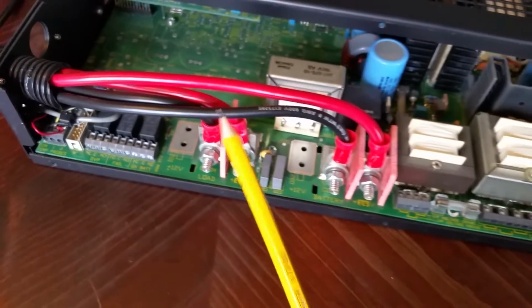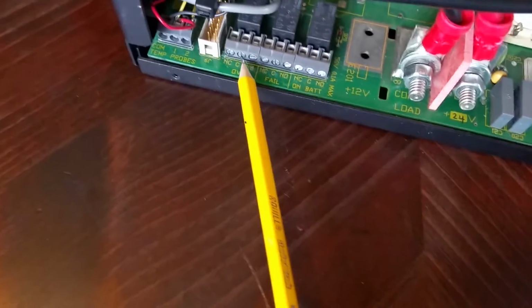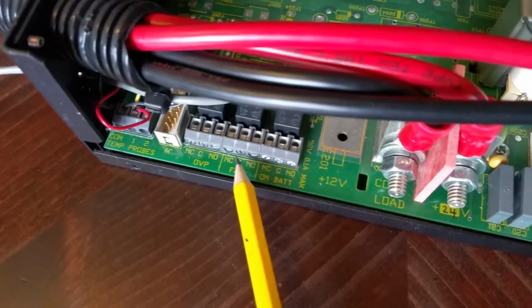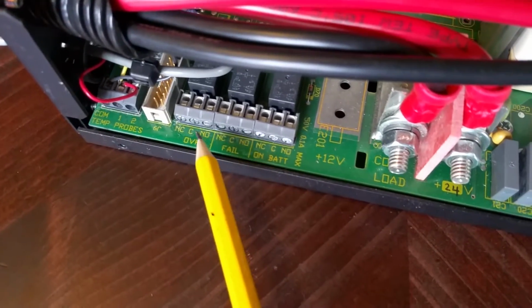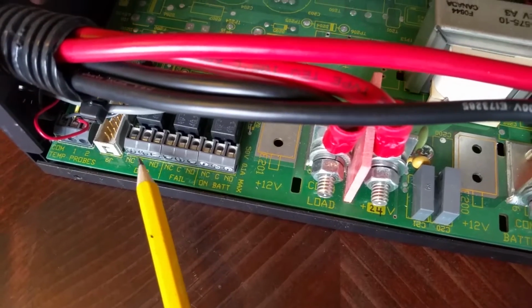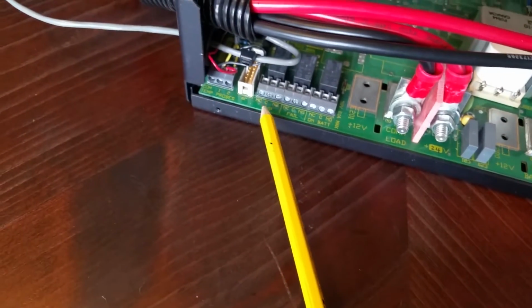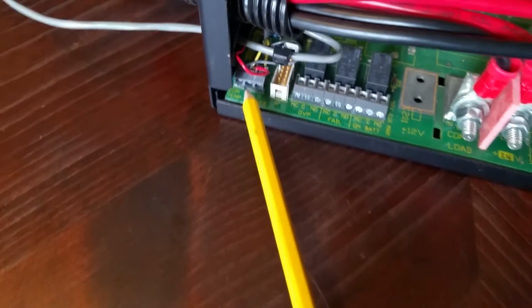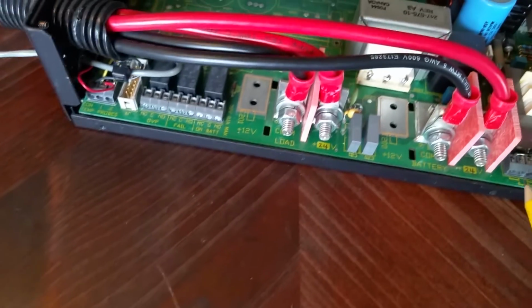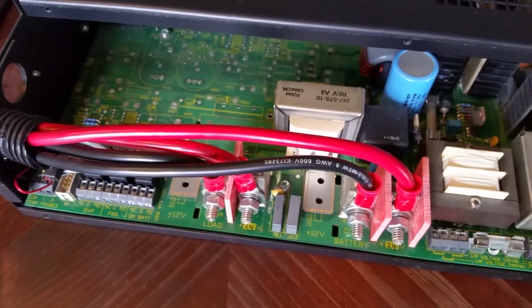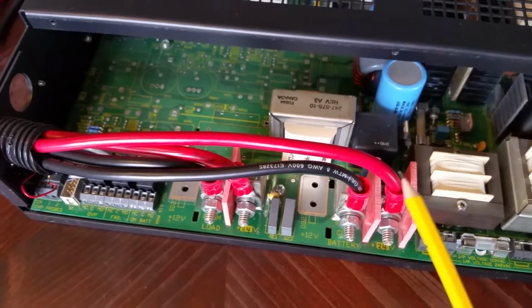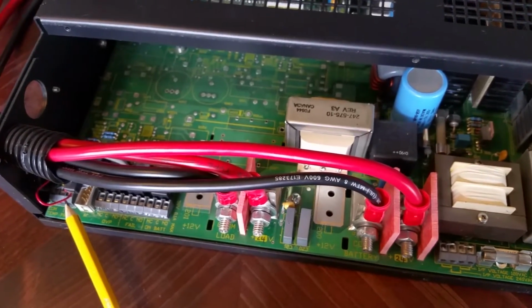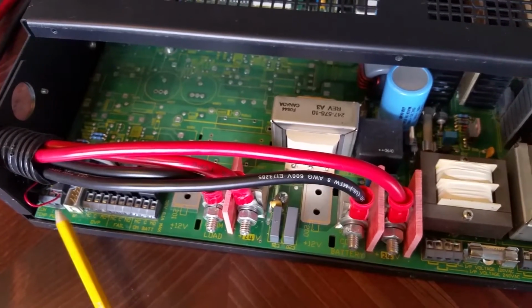This is a great feature, and you can do things like a battery alarm, similar to a camera system that gives you alerts for everything. You can connect this stuff right here and a temperature sensor right here that tells the system, hey, don't pour too much current into this battery because it's getting too warm or too hot. Instead of the batteries being overcharged, the temperature sensor, just like on any Midnite Solar or outback system, tells the charger to slow down.